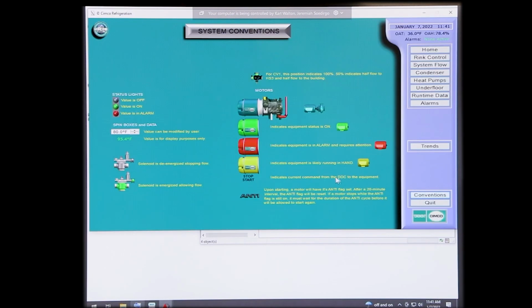Under conventions, we have what you'll see when you look at the screen. If it's yellow, somebody has put something in hand. If it's red, it's an alarm. If it's green, it's supposed to be running and is running. And if it's normal color, blue, it's not yet been called. Okay? And you'll see some other things in here, some green lights, some turn on for valves. It's a pretty generic page, just covers a lot of things. Your anti-signal here, which you'll see when we bring a compressor online. Again, when you're done on this page, you want to quit down here, not X out. You should only X out on trend logs, but you will quit here.